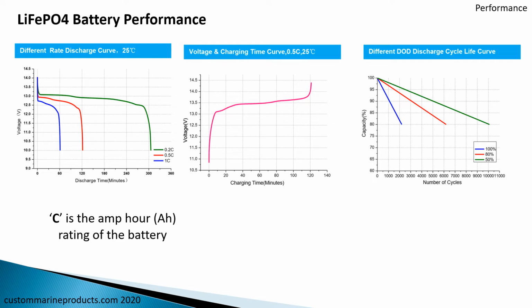depth of discharge chart is very interesting in these. And basically what this says is that if we discharge our battery 100% at a given rate, we'll still get 2,000 charge-discharge cycles out of the battery. If, on the other hand, we draw it down 80%, we'll get upwards of 6,000 charge cycles. And if we only draw it down 50%, you can get over 10,000.